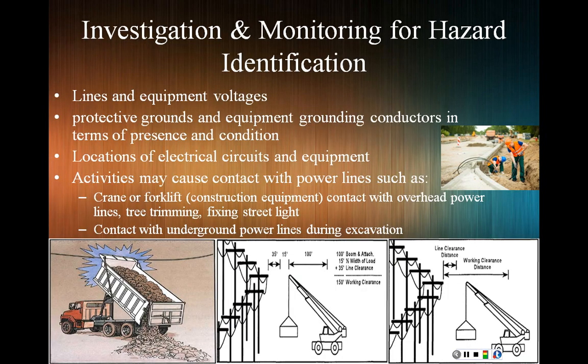Investigation and monitoring for hazard identification. We should know about the voltage of lines and equipment. We should monitor and investigate the presence and condition of grounds and equipment grounding conductors. Grounding in high voltage is the same as low voltage. The logic behind this is to provide a more conductive path for the electrons to go through to the ground.